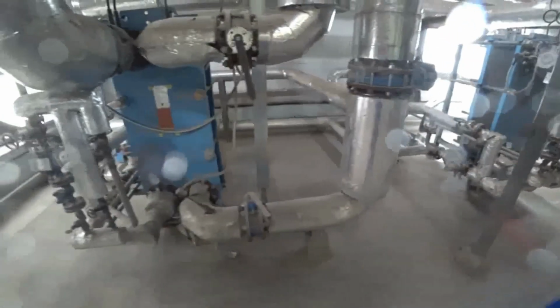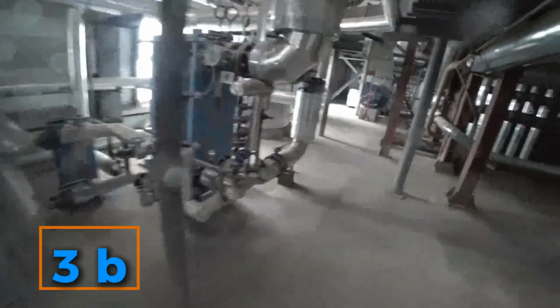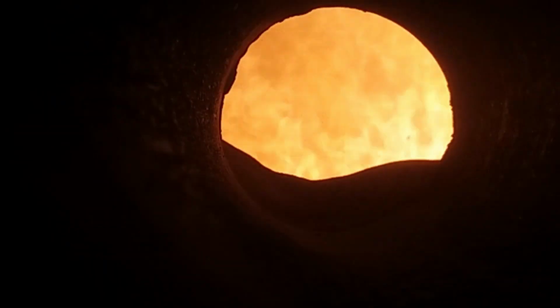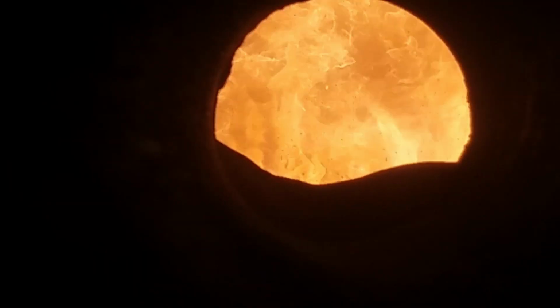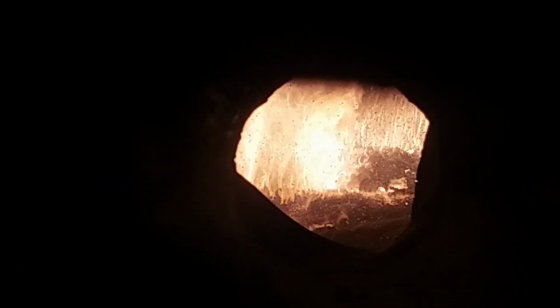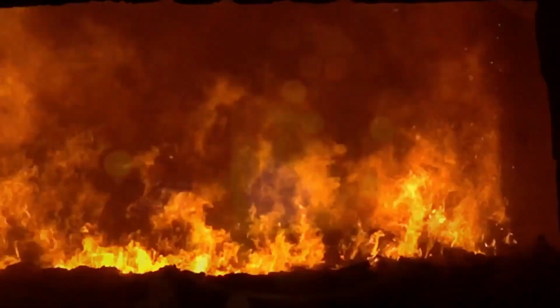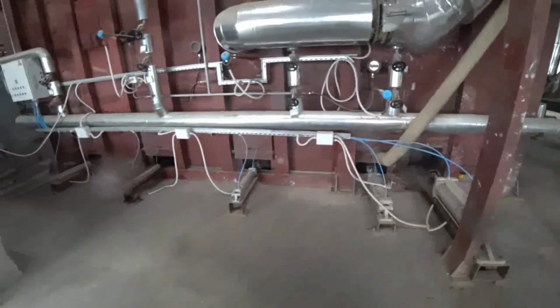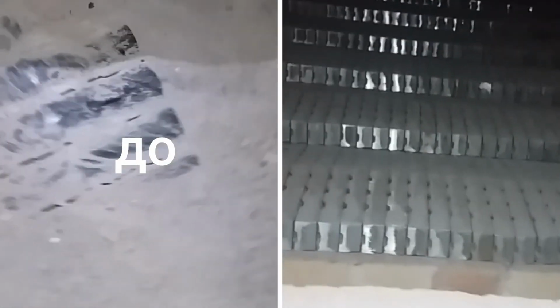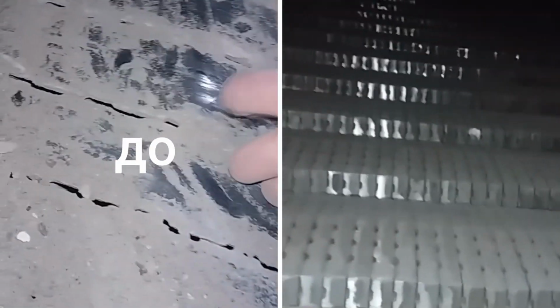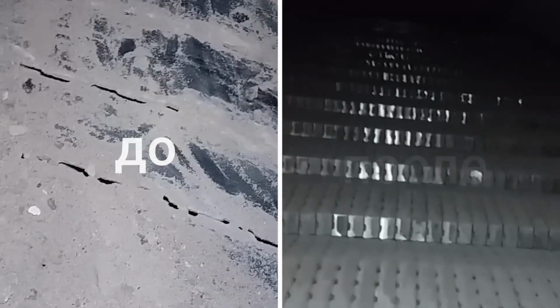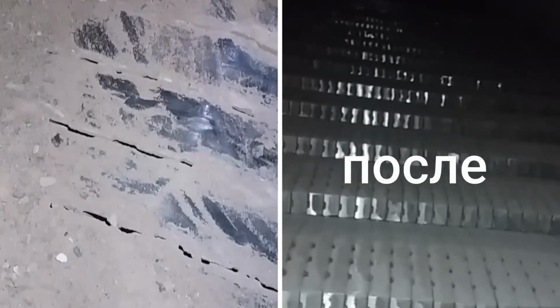2 plate heat exchangers are installed to heat the hot water. The capacity of each is 8 megawatts. Heating medium, steam with a pressure of 3 bars. And now we will see how chicken manure burns in our boiler. This boiler, manufactured in 2017, had spill grates and accordingly required an ash removal system from under the furnace. Since 2018, all boilers have been equipped with non-spill grates.